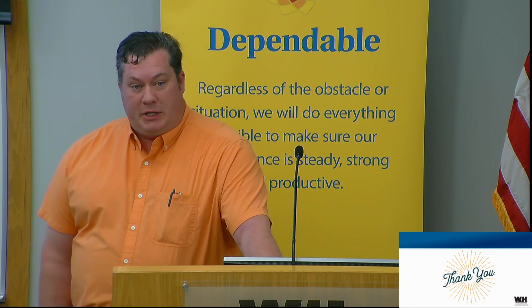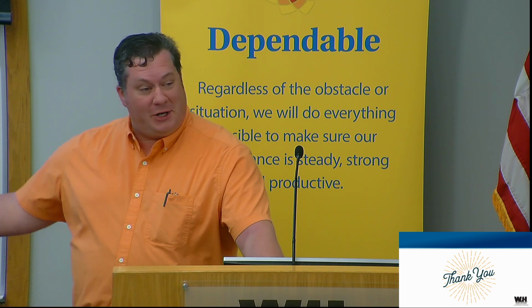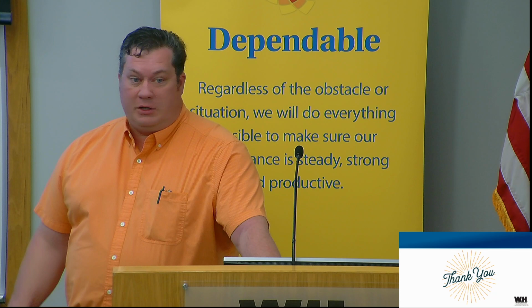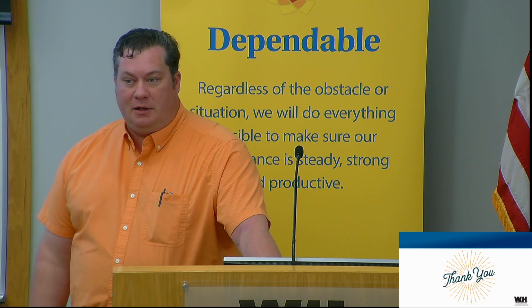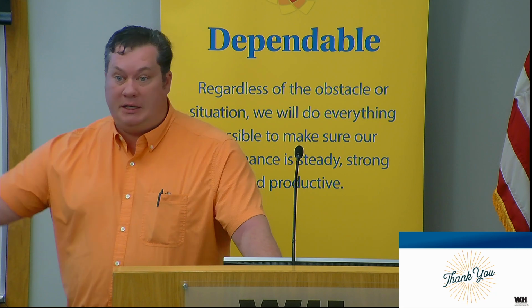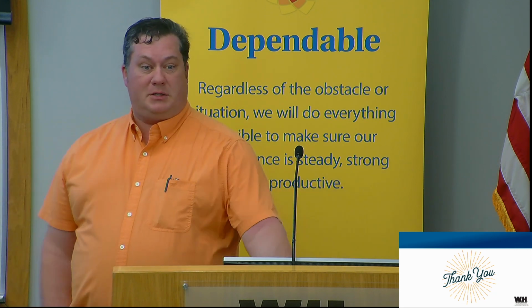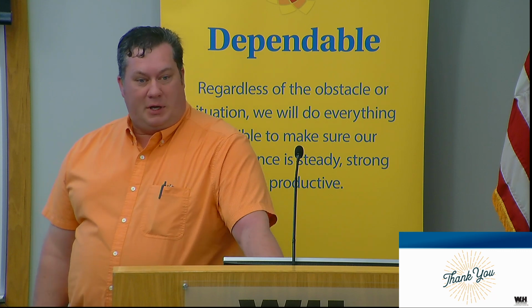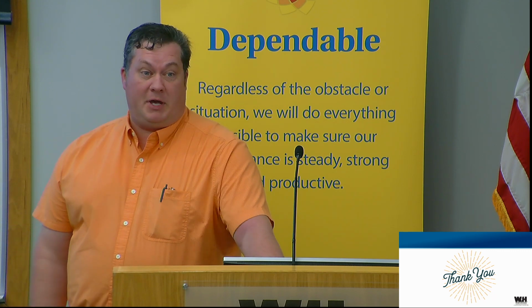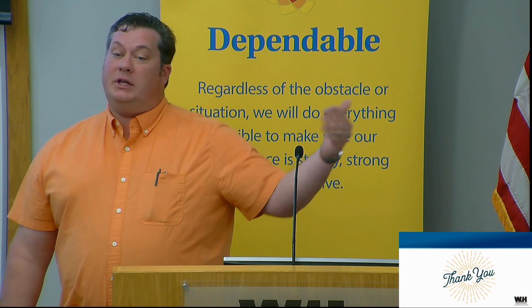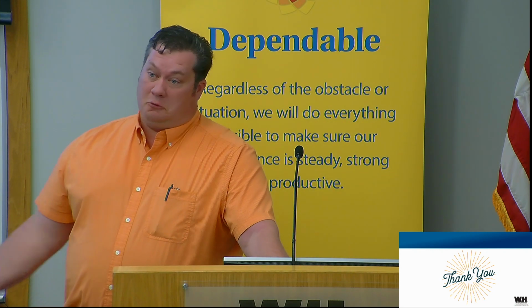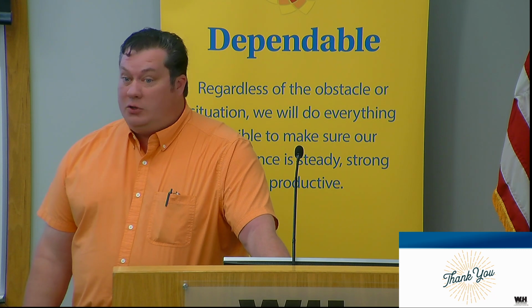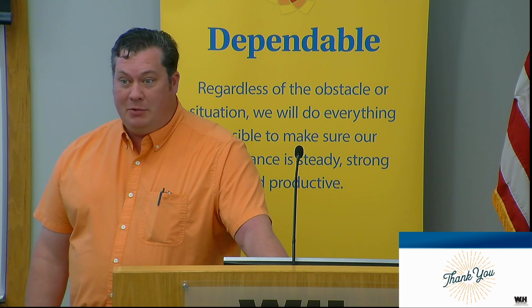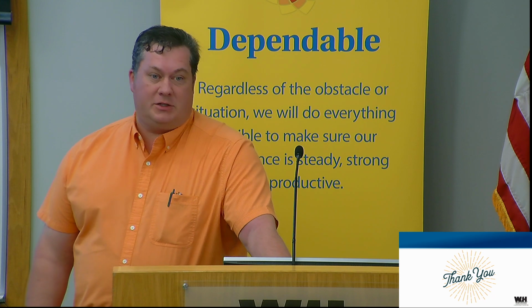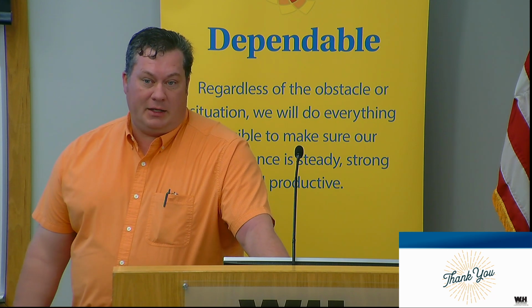They're going to allow NM in there. If you've inspected under me or anybody else 5+ years ago, in your mind you'd think you gotta rewire with AC/MC cable, right? You can't have NM exposed in a multifamily detached garage, like one of these long 20-space garages. But we got a bulletin that tells you otherwise. It basically says, if you've got a multifamily garage, we're gonna let you wire that with NM cable just like a regular single-family garage. If you don't know that, and you bid this job thinking you gotta use AC/MC cable because it's not a 1 or 2 family residential garage, and you bid it against somebody who knows about the bulletin, you're probably gonna lose the bid.